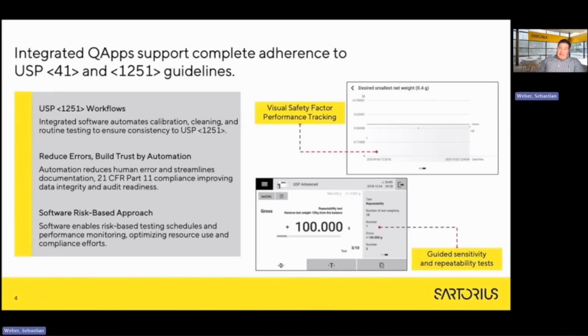When we go to the software part, we were asked by USP 1251 to follow more of a risk-based approach for calibration, for routine tests, and also the documentation around it. And here, software can help a lot. The software, for example, can schedule these tasks, guide the user step by step on the screen, and store the results automatically, all in 21 CFR Part 11 compliant use. For example, you can configure a good weighing system so that it blocks weighing or doesn't document weights if the daily test was not done, then guides the user to complete, for example, the repeatability test, and then enables him to resume work.